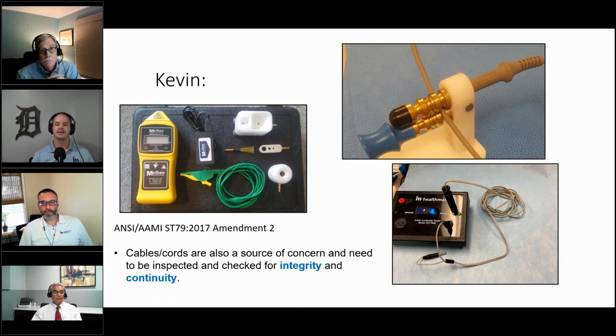So the new ANSI AAMI ST79 amendment states that cables and cords need to be inspected for integrity and continuity. So what does that mean exactly? You see that same insulation tester to the left of the screen, and we can use the accessory on the upper right of the slide to test the insulation of monopolar and bipolar cautery cords. This is going to ensure that the cord is free of defects in the insulation, so all that electricity going through there stays within the cord safely as intended, should you be adopting this practice and testing all your cords.